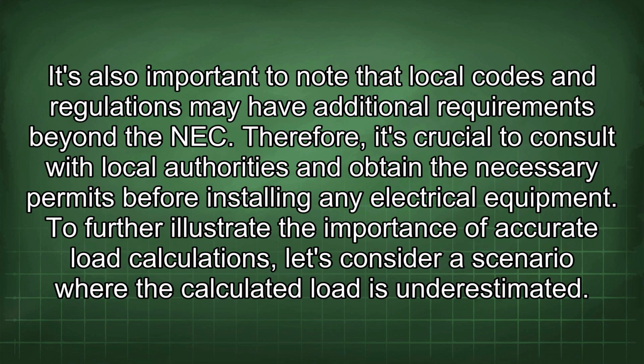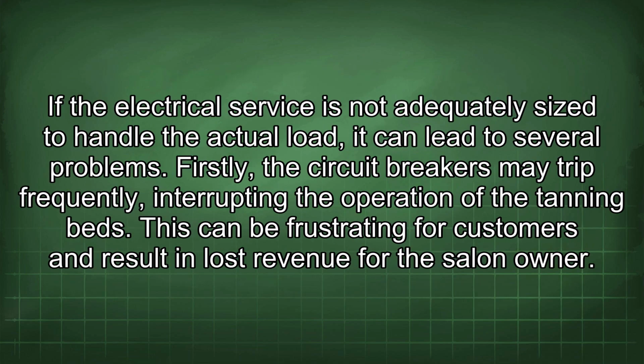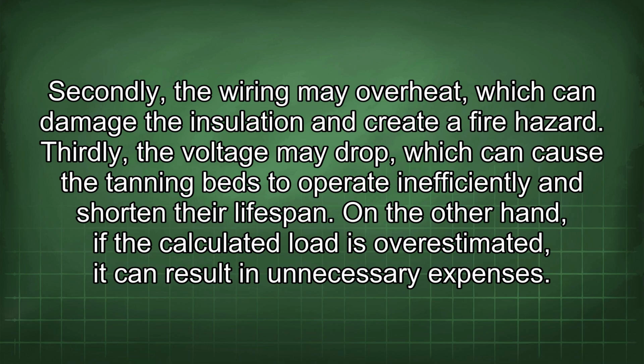To further illustrate the importance of accurate load calculations, let's consider a scenario where the calculated load is underestimated. If the electrical service is not adequately sized to handle the actual load, it can lead to several problems. Firstly, the circuit breakers may trip frequently, interrupting the operation of the tanning beds. This can be frustrating for customers and result in lost revenue for the salon owner. Secondly, the wiring may overheat, which can damage the insulation and create a fire hazard. Thirdly, the voltage may drop, which can cause the tanning beds to operate inefficiently and shorten their lifespan.